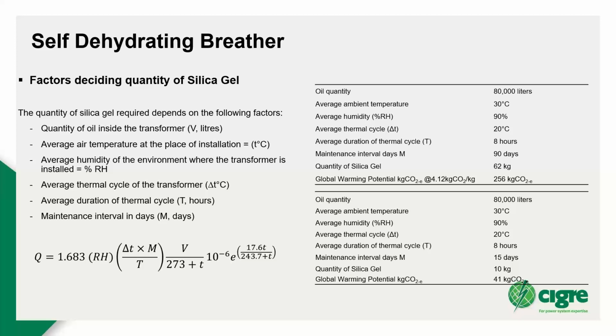In the example on your right, I've shown one calculation. Let's say we have 80,000 liters with very high humidity, and we want to maintain it every 3 months - you'll probably need a lot more silica gel, which adds to your global warming potential and to the total life cycle carbon footprint analysis of your transformer. If you reduce the maintenance interval from 90 days to 15 days, you bring the 62 kg down to 10 kgs.